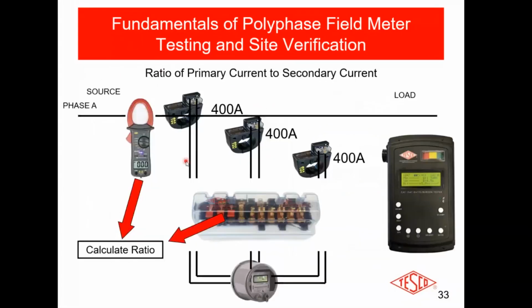What's the other thing that you want to check? The other thing you want to check is the ratio. Why do you want to check the ratio? You want to check the ratio because if you have an incorrect ratio out there, if I tell you that I've got a 400 to 5 transformer, but really I have an 800 to 5 transformer out there in my service, that means I'm only going to be giving half of the bill. I'm going to be losing 50% of the revenue, all right? The ratio, it's pretty simple to do. You can use a piece of equipment like ours or any of our competitors, or if you have access, you can get some ammeters.